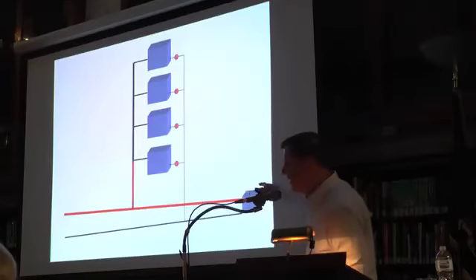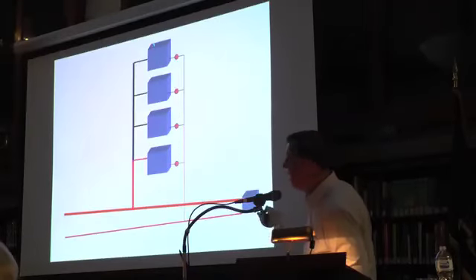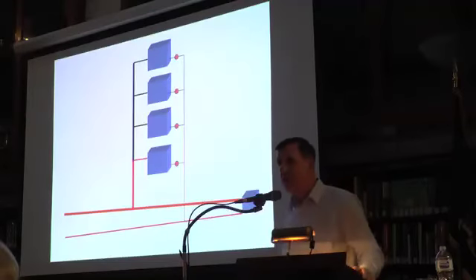So you get this, it goes down the end of the line, and suddenly it passes through the radiator and into the return. Now you see here we've got steam in both the supply and the return, and none of these radiators will get hot because the air is trapped in them. So this is where some knucklehead goes in and puts one-pipe steam air vents on those radiators up there.